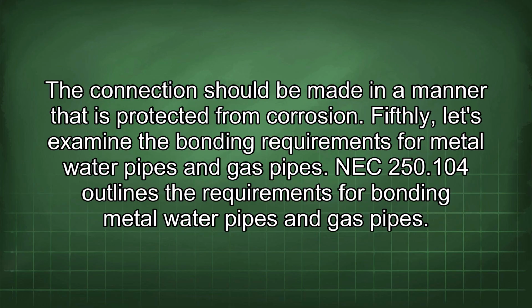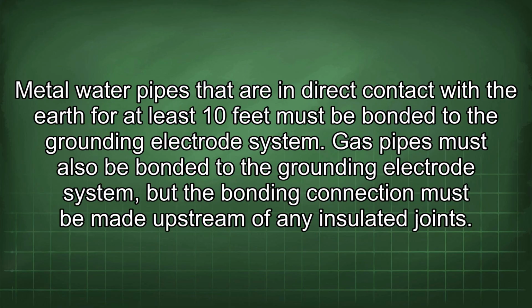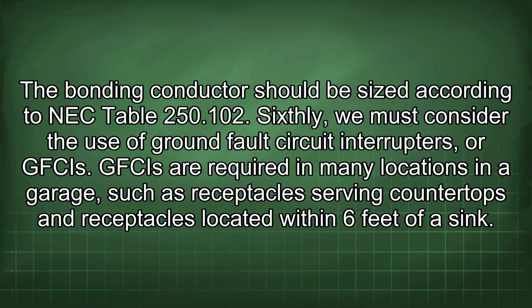Fifthly, let's examine the bonding requirements for metal water pipes and gas pipes. NEC 250.104 outlines the requirements for bonding metal water pipes and gas pipes. Metal water pipes that are in direct contact with the earth for at least 10 feet must be bonded to the grounding electrode system. Gas pipes must also be bonded to the grounding electrode system, but the bonding connection must be made upstream of any insulated joints. The bonding conductor should be sized according to NEC Table 250.102.